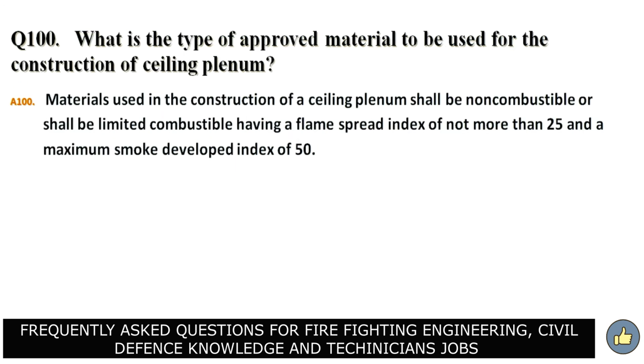What is the type of approved material to be used for the construction of ceiling plenum? Answer. Materials used in the construction of a ceiling plenum shall be non-combustible or shall be limited combustible, having a flame spread index of not more than 25 and a maximum smoke developed index of 50.